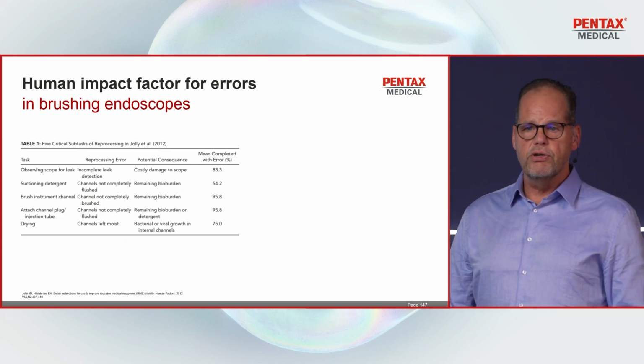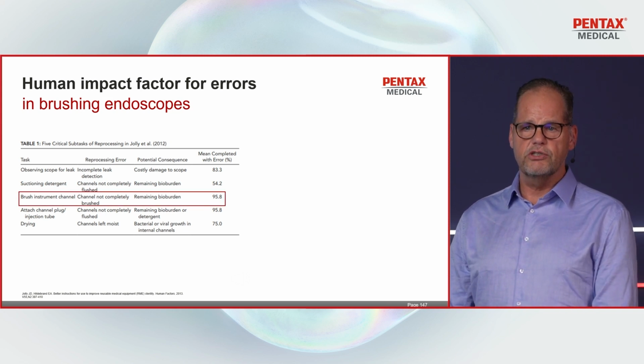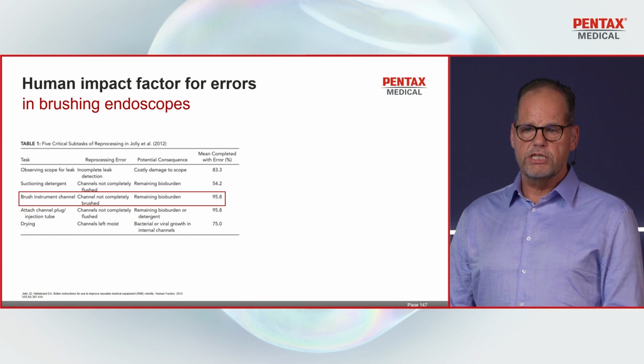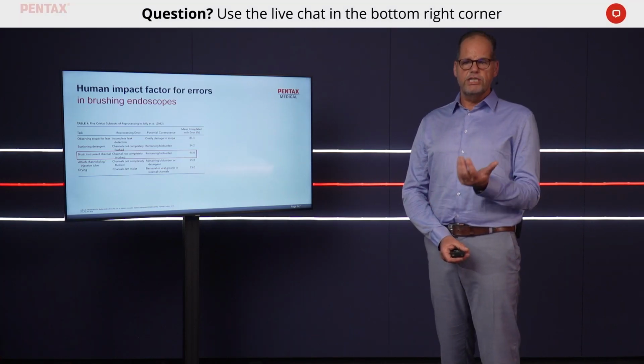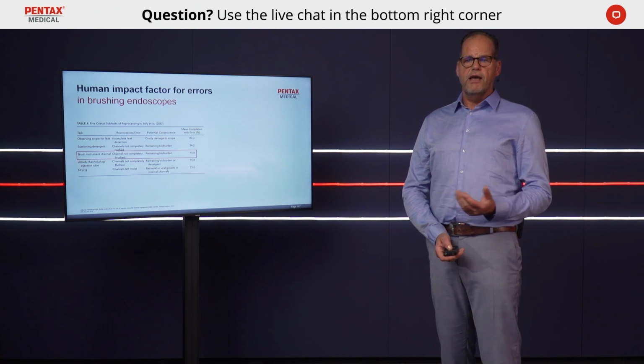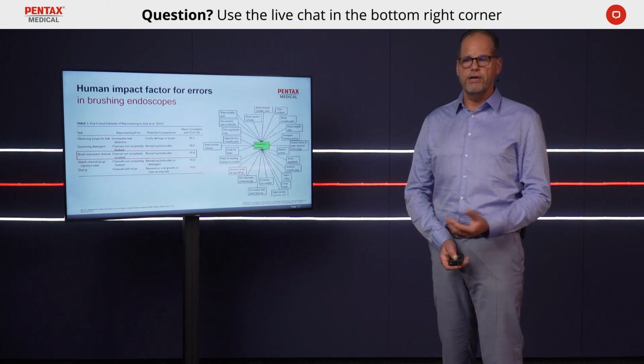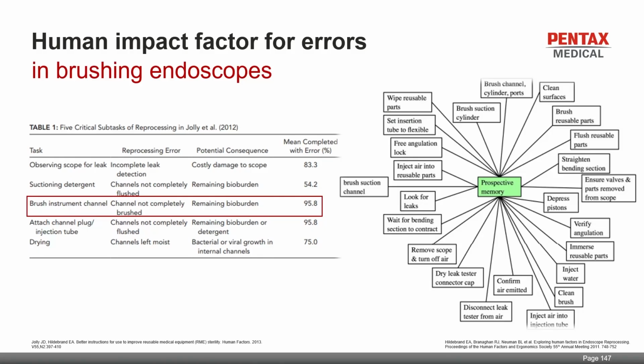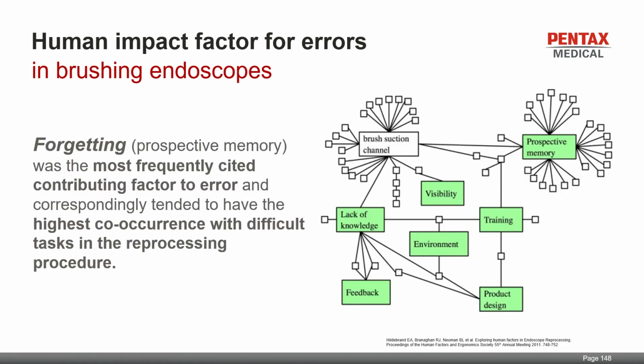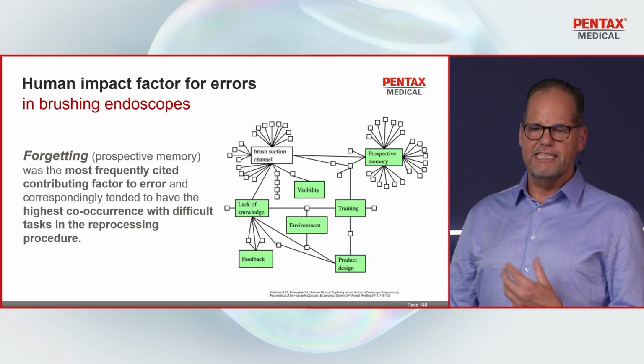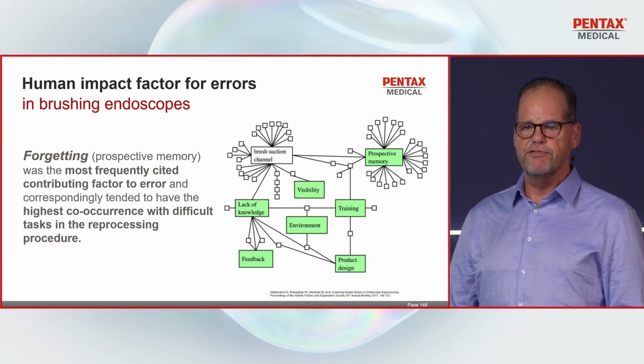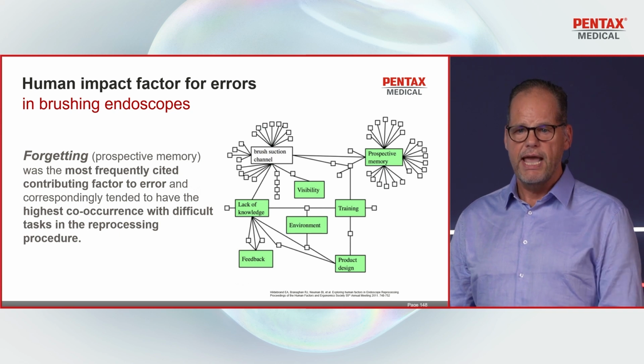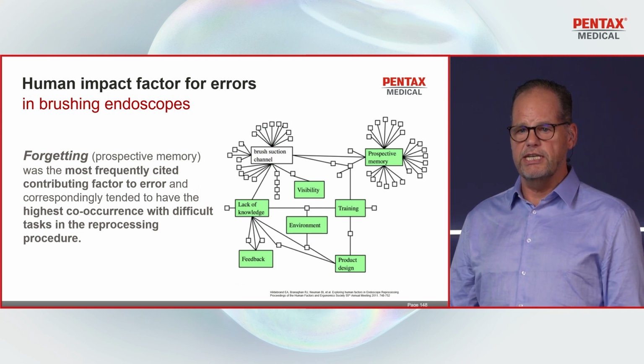Let us have a deep look at the brushing, because that is one of the factors which is prone to human error. There was a study in 2012, and we see here that 96% of the brushing is not done in the right way, so leading to errors. And if you look at the mind of the reprocessing staff, these are all factors which are involving all those human impact factor and failures in endoscope brushing. What was very nice is that this study showed that forgetting is the most frequently cited contributing factor to error and the highest co-occurrence with difficult tasks in the reprocessing procedure.